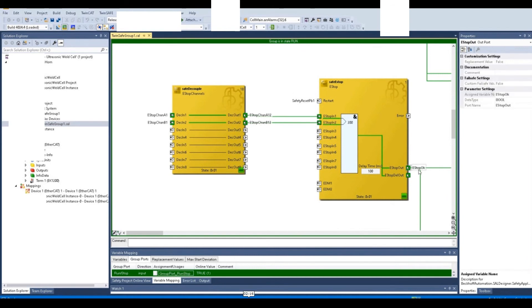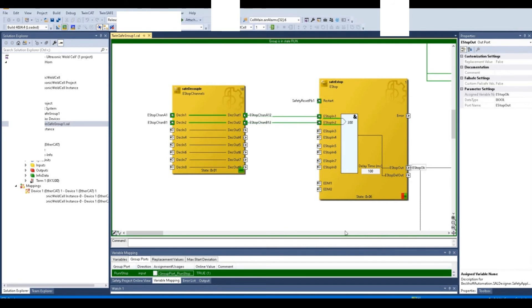The reset signal needs to go from 0 to on, and then from on to off — that change is required. Let's watch this process again: now the e-stop is OK, we press e-stop, then release the e-stop — e-stop OK output is still off. Let's watch carefully about the reset signal: turn on, then look at the corner color change — once reset goes off again, the e-stop OK recovers. This is the whole process.